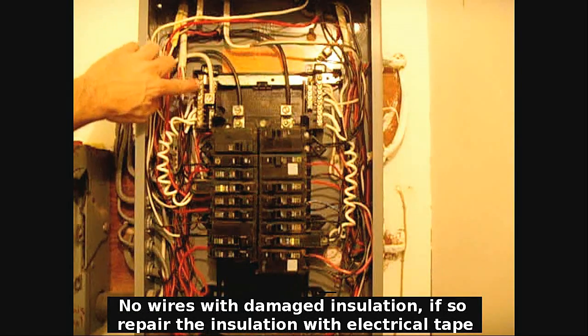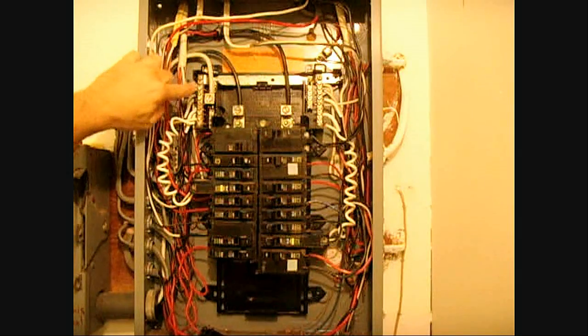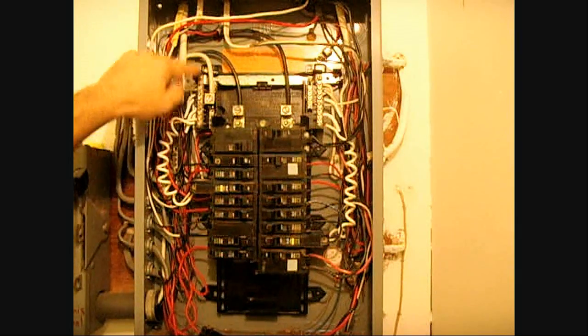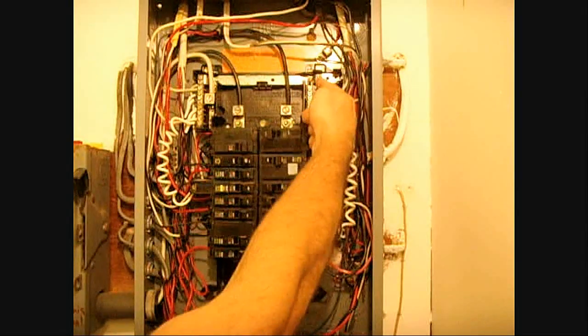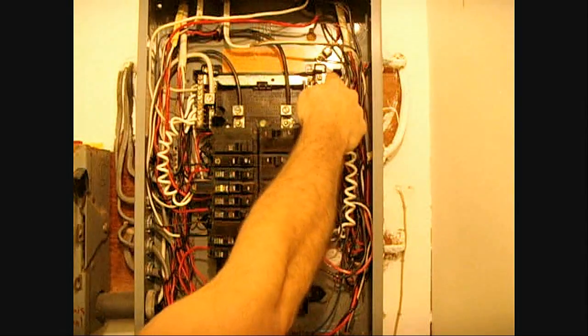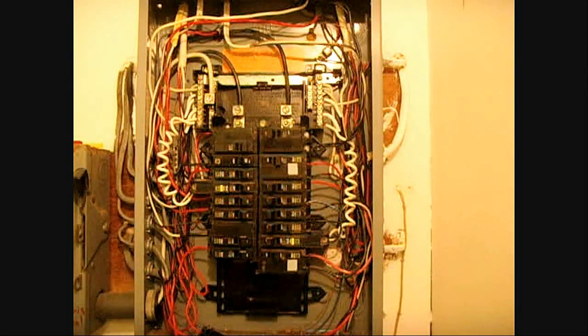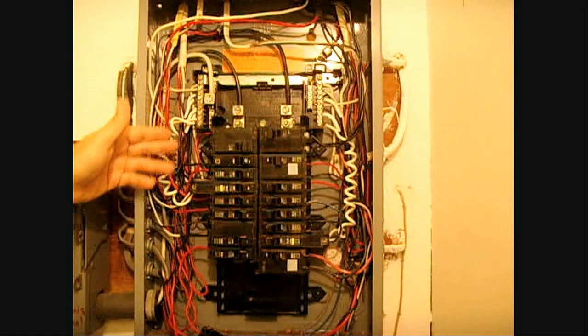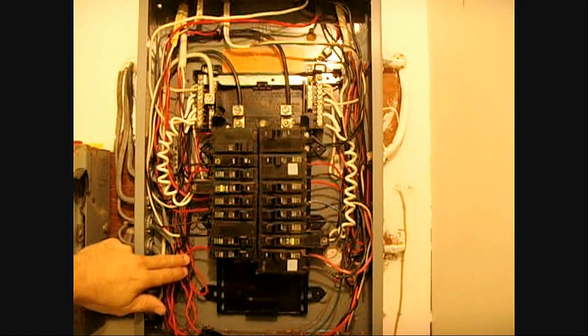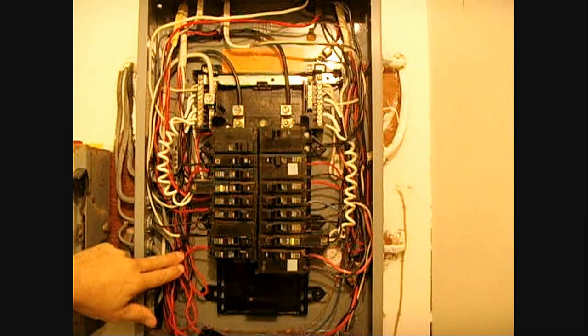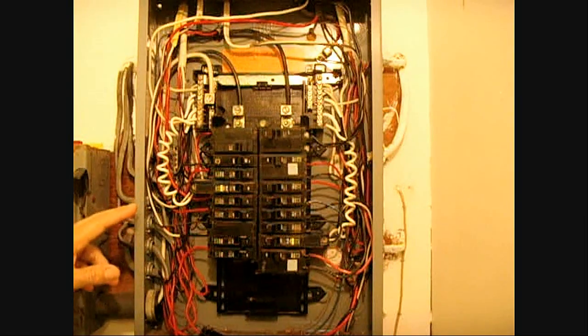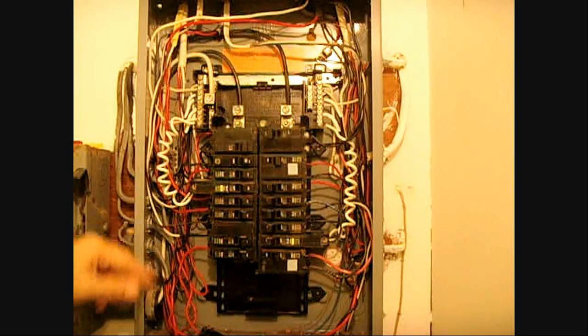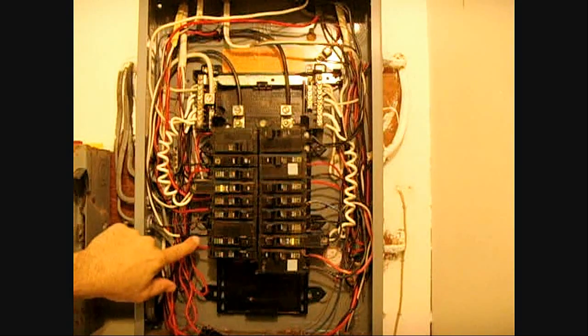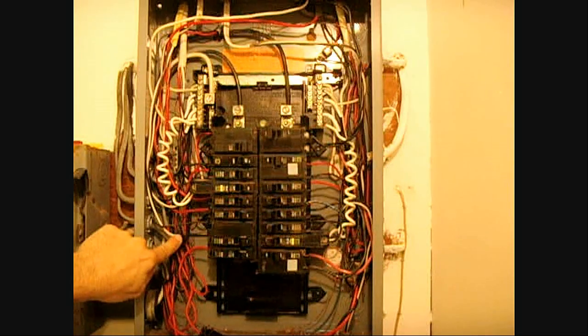You could take a Phillips screwdriver on any of the neutral bars while power's on. Tighten these screws down securely. Check that screw there. Make sure that this bar with all these terminals is securely fastened to the top neutral bar. You don't want anything loose. Every single wire attached to your breakers must be a red, black, blue, yellow, orange, any of those colors. You don't want to see any whites, you don't want to see any grays. If you see white or gray on here, make sure you wrap it like you see here with black electric tape. This way it's marked as hot.